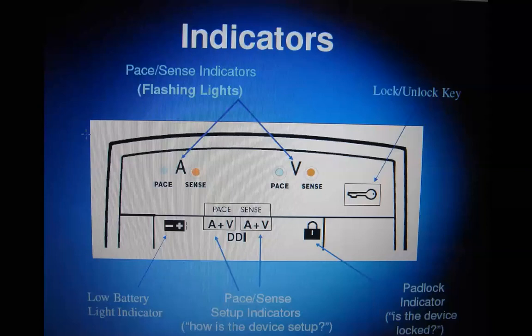Then I have to start with this slide, as I said, to show us that this is a dual chamber temporary pacemaker machine, and that you can see the A and the V representing the two chambers, atrium and ventricle. For both chambers, you can see both pace and sense indicators. So if your lead is inside any of the chambers, if it is pacing, it will show the light indicator to show pacing, whether in the atrium or in the ventricle. Also if it's sensing, it will be a blinking light. So these indicators are for blinking the light.